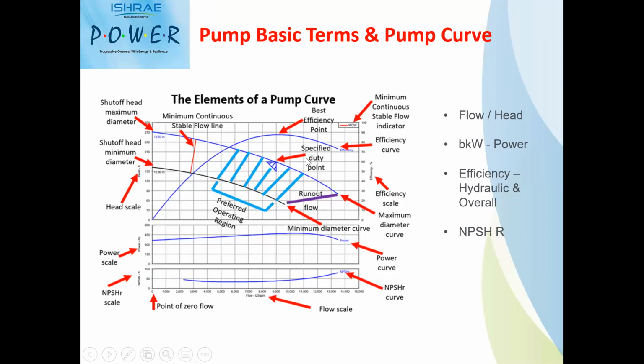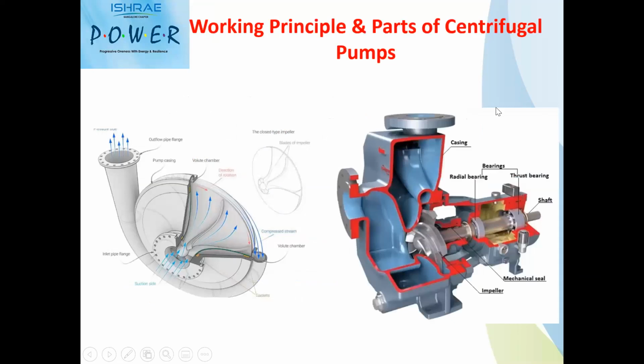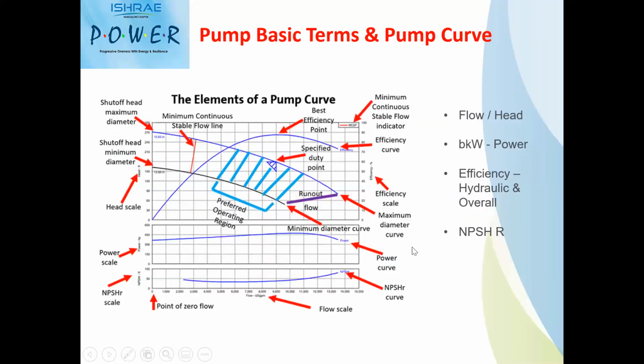Then any kind of pump, for that matter, is identified by the suction and discharge sizes as well as the impeller sizes. For example, you require a pump of 1000 US GPM at 20 meters head. When we select a typical pump with these performance curves, the pumps are selected based on flow rate, which decides the suction size of the pump, this size, and the head value.